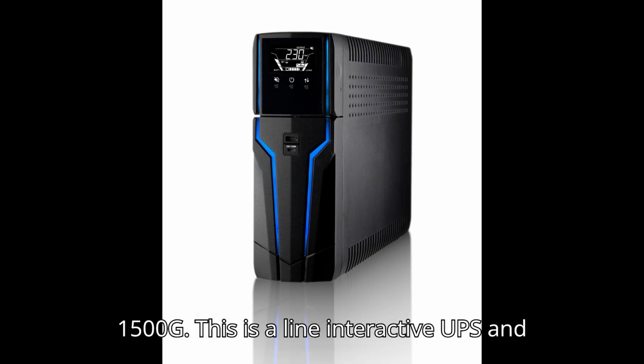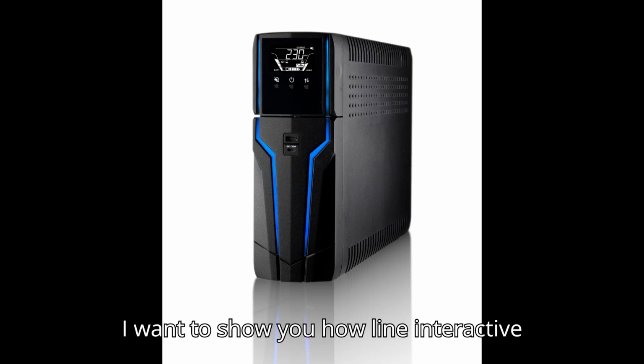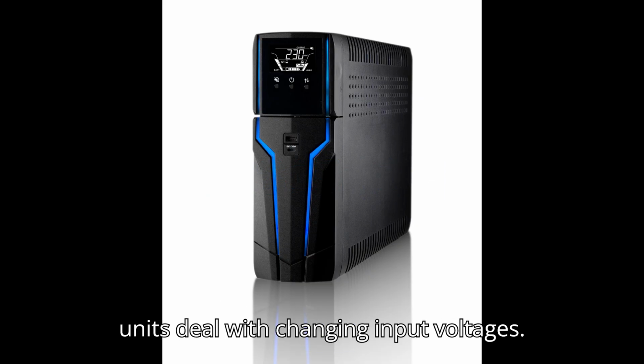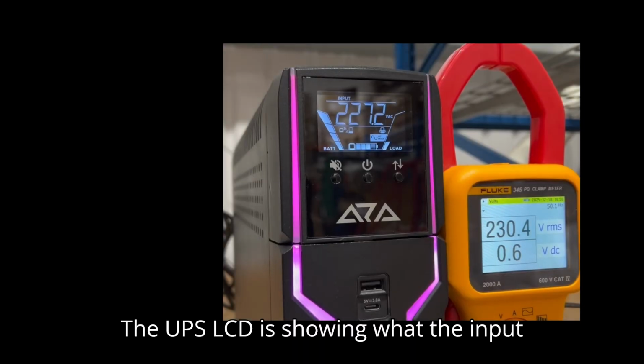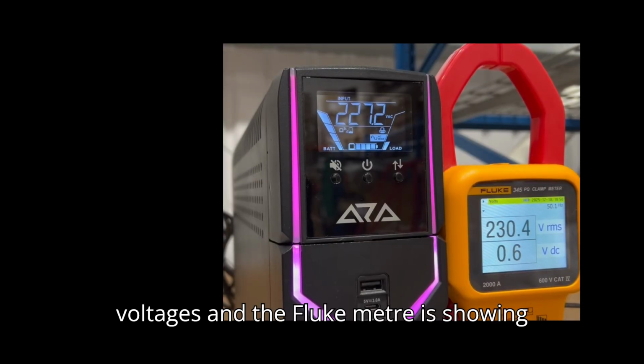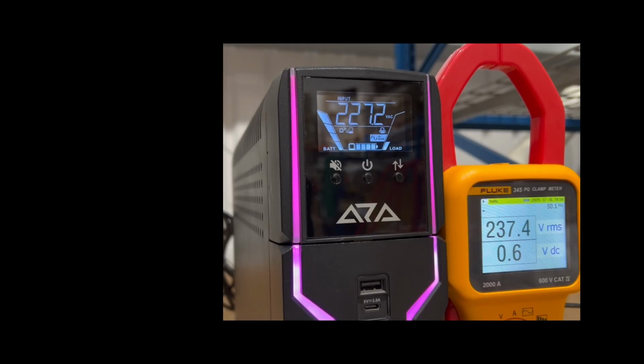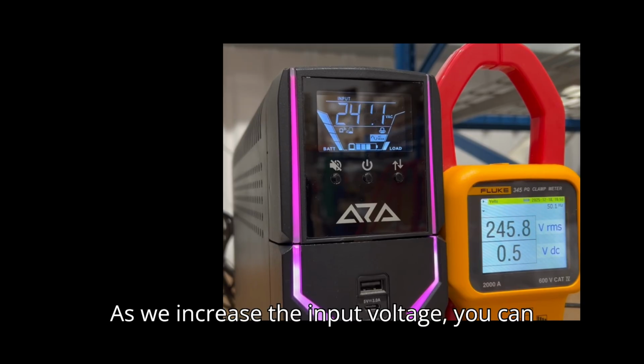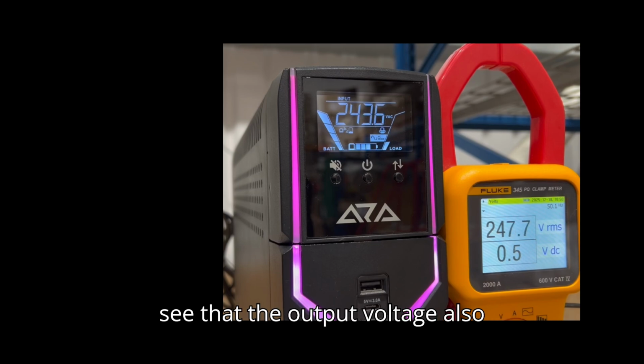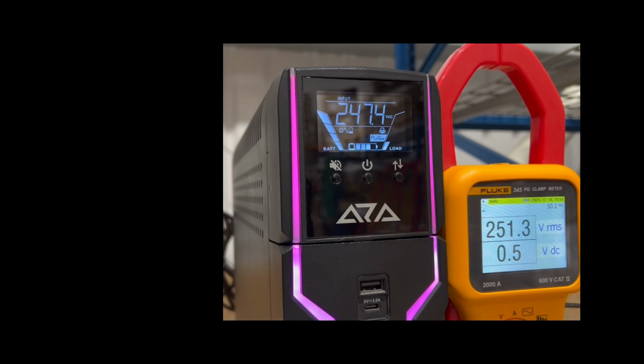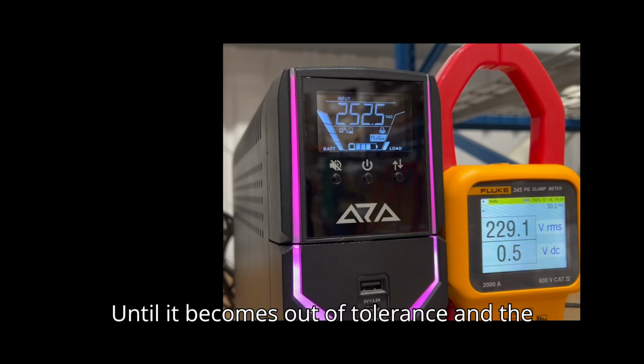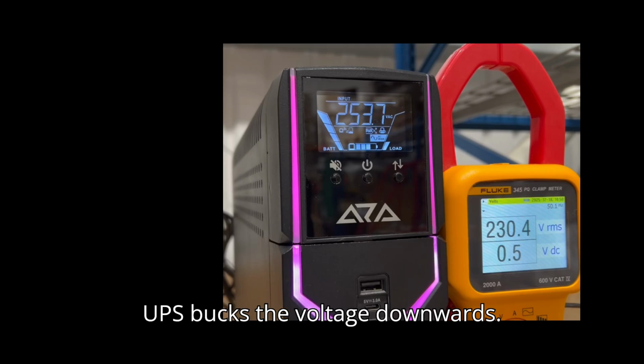This is a line interactive UPS and I want to show you how line interactive units deal with changing input voltages. The UPS LCD is showing what the input voltage is, and the Fluke meter is showing what the output voltage is. As we increase the input voltage, you can see that the output voltage also increases, until it becomes out of tolerance and the UPS bucks the voltage downwards.